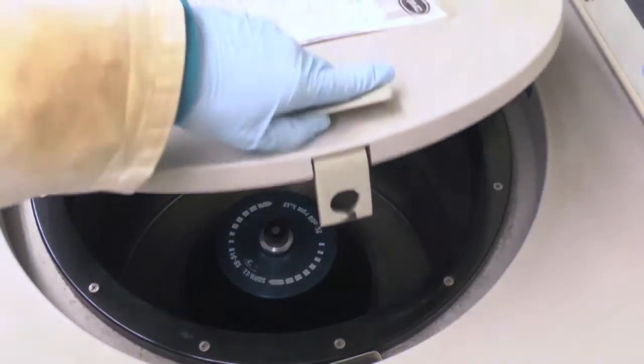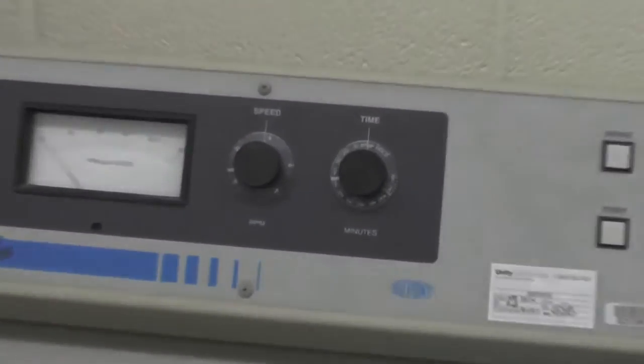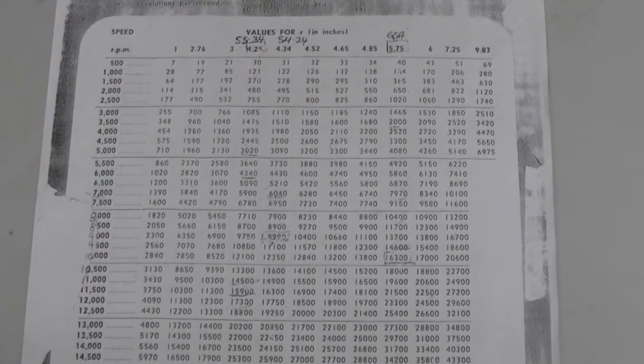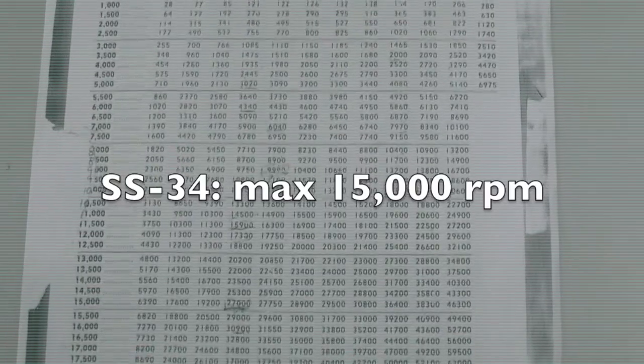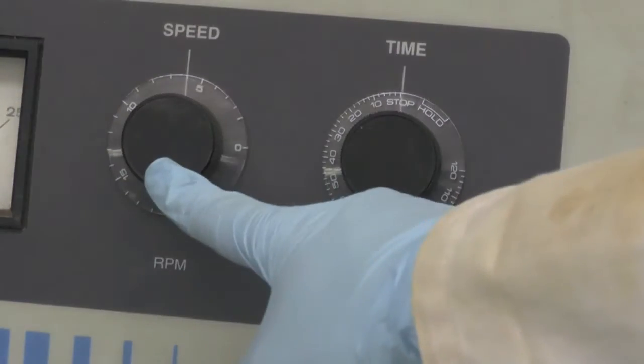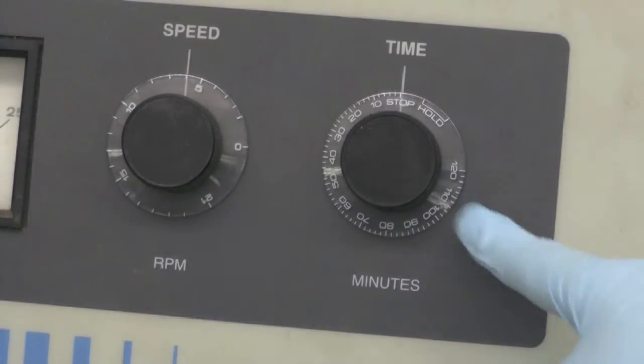Close the chamber door. Set the appropriate speed in RPM using the control dial. The gravity conversion can be found on the chart posted on the chamber door. Note that the center part contains all the universal G-force value, while the top row describes type of rotor and the left column displays the RPM for the centrifuge setting. Maximum speed for the SS34 is 15,000 RPM. Set the time desired for the run using the time control dial.